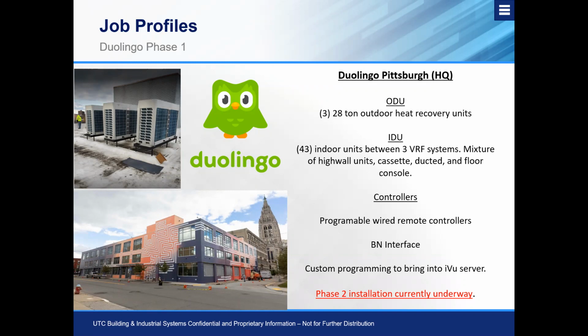So on our first phase, we had three 28-ton recovery units with a total of 43 indoor units between those three outdoor systems. We have a mixture of high wall units, cassette units, ducted units, and floor consoles. For controls, we have all programmable wired remote controllers for each indoor unit. And the outdoor unit then sends that data to our backend interface, which is set up with a custom program that is integrated into a system that is controlling the entire building between rooftop units, VRF units, and outside air units. Currently, we have phase 2, which is four 28-ton machines that we're dealing with.